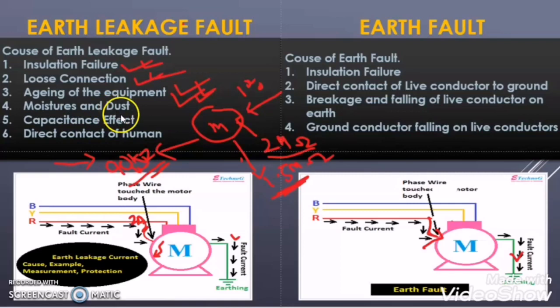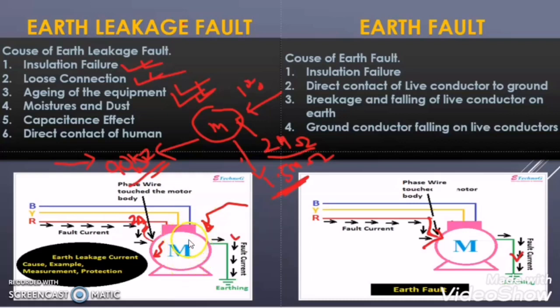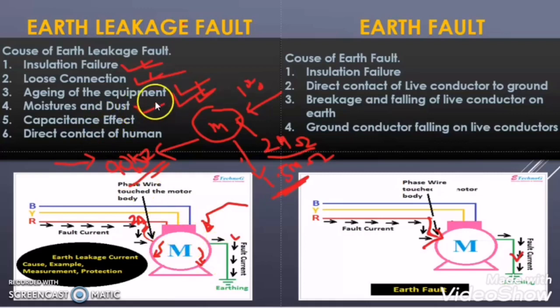The fourth condition is dust or moisture. Suppose the motor is new, everything is perfect — there is no loose connection, there is no insulation failure. But the motor is in an atmosphere with too much moisture. So the moisture will accumulate in the motor winding and it will reduce the insulation of the motor winding. When we run the motor, it will spill some amount of current to the body of the motor. So moisture and dust are also reasons for earth leakage fault.